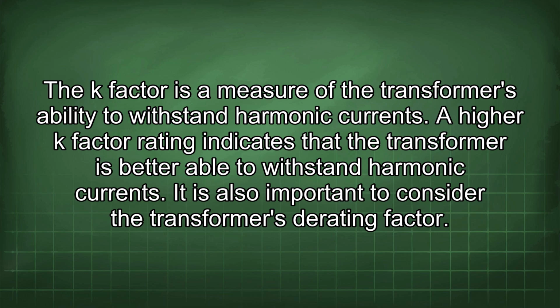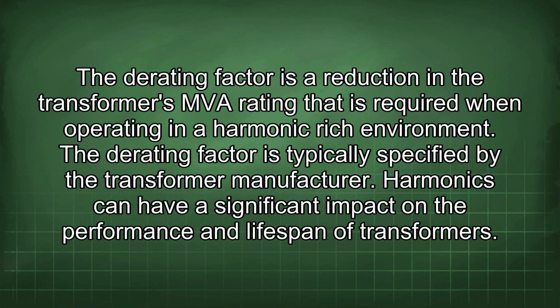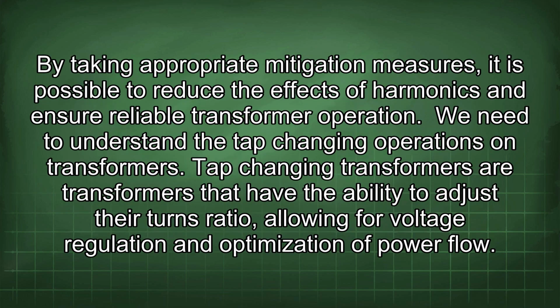It is also important to consider the transformer's derating factor. The derating factor is a reduction in the transformer's MVA rating that is required when operating in a harmonic-rich environment. The derating factor is typically specified by the transformer manufacturer. Harmonics can have a significant impact on the performance and lifespan of transformers. By taking appropriate mitigation measures, it is possible to reduce the effects of harmonics and ensure a reliable transformer operation.